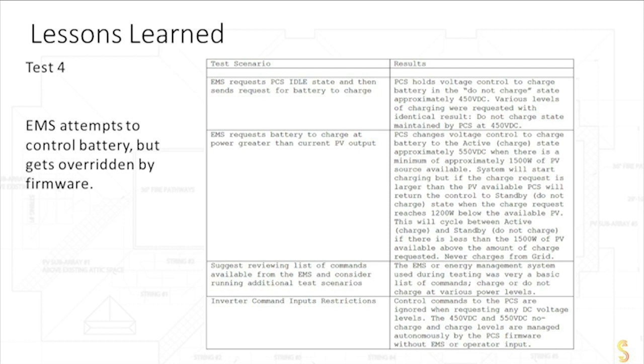Utilities and regulators typically don't like it like that. So this gives assurance that even if there's another brain or another piece of software in the system somewhere, like in an EMS, whatever it does, the firmware is going to take control. And so even though EMS and firmware, or software and firmware, are both types of software, you could define the difference as one is inherently non-adjustable.